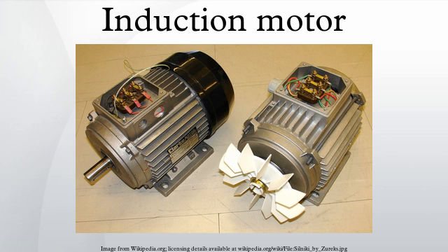The ratio between the rotation rate of the magnetic field induced in the rotor and the rotation rate of the stator's rotating field is called slip. Under load, the speed drops and the slip increases enough to create sufficient torque to turn the load. For this reason, induction motors are sometimes referred to as asynchronous motors. An induction motor can be used as an induction generator, or it can be unrolled to form a linear induction motor which can directly generate linear motion.